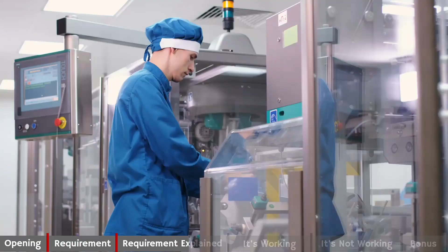Like all validations, we will have an IQ protocol and we will have an IQ report. And again, that protocol has to be approved with our pre-approved acceptance criteria before we start the validation. And then finally, the IQ is not complete until the report is signed off. At most companies, the IQ templates in the procedure will be a series of checklists that will capture all of this information and make sure that you get everything done during the installation qualification.